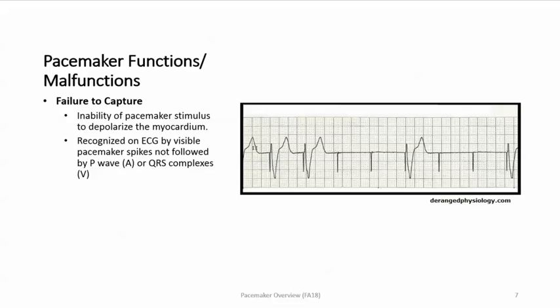The next malfunction is failure to capture — this is the inability of the pacemaker stimulus to depolarize the myocardium. The pacemaker fires but no depolarization occurs. It is recognized on the ECG by visible pacemaker spikes not followed by a P wave in atrial pacing, or QRS complexes in ventricular pacing. The pacemaker sent the signal but nothing happened.